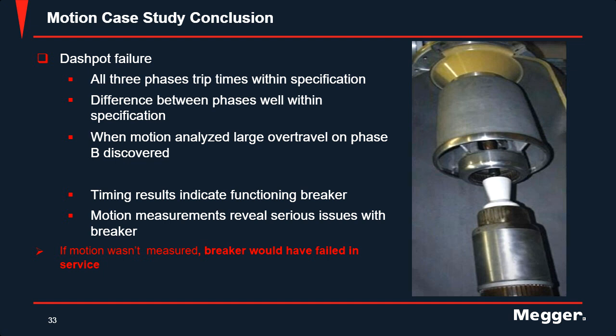Yes, hooking up the transducer to your breaker can be a headache at times, depending on what type of breaker you have. You also need to plan ahead. So once you figure out, hey, we need to test this breaker, you need to look up the model and find the manufacturer specs for what transducer you should use, so that you're already ready before you show up. It adds more time to your test, but as we just saw, just because the timing comes in correctly does not mean that you don't have overtravel or rebound on your traveling mechanisms, and you won't catch that unless you do a motion or travel analysis.